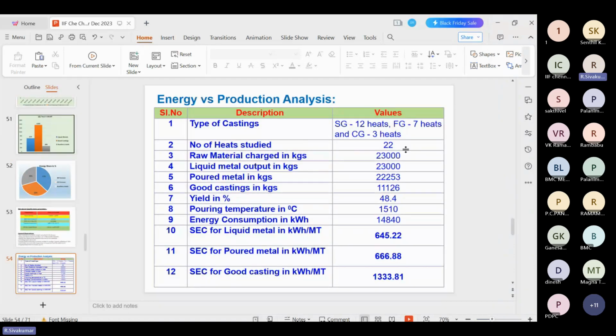In total, 22 heats were continuously monitored with the power quality analyzer at the main input, the transformer primary. The 22 heats were studied for almost 1 day, 24 hours. Raw material charge is 23 tons, liquid metal output is 23 tons, poured metal is 22,253 kg, good casting is 11,126 kg, yield is 48.4%, and the average pouring temperature is 1510 degrees.